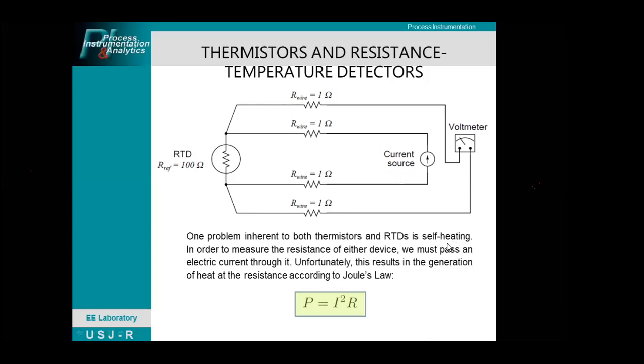The problem inherent to both thermistors and RTDs is self-heating. In order to measure the resistance of either device, we must pass an electric current through it. That's why they have this current source, symbolized as the current source. The result is the generation of heat in the resistance according to Joule's law, which is equal to I squared R. The power is equal to I squared R, the square of the current passing through times the resistance, so that will determine the power or the heat produced in these RTDs.